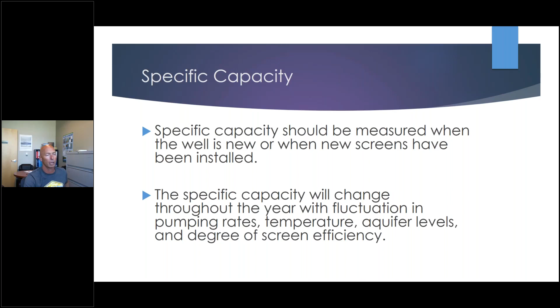A drop of 5% in specific capacity indicates problems with a well. We've seen wells at 3% started to show problems. Now this is on a very large system. They were pumping at over 1,000 gallons per minute. They noticed it right away because the 3% in a 1,000 gallon per minute well is a huge number that they're losing. So they want to catch it right away. So catching the problems at an early stage gives us the best chance of well rehab.